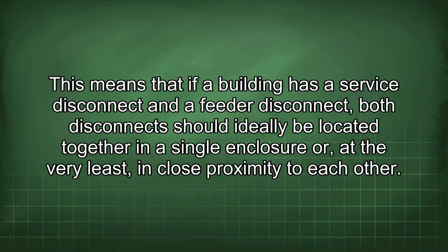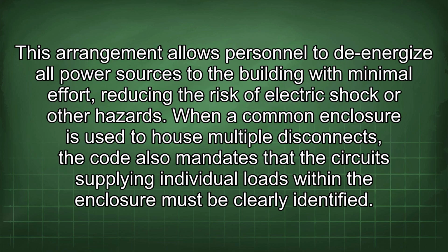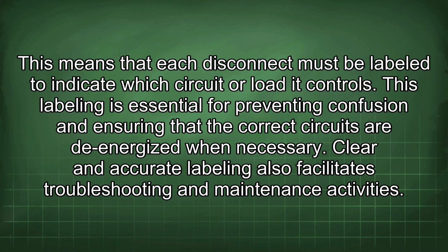serve. This means that if a building has a service disconnect and a feeder disconnect, both disconnects should ideally be located together in a single enclosure or, at the very least, in close proximity to each other. This arrangement allows personnel to de-energize all power sources to the building with minimal effort, reducing the risk of electric shock or other hazards. When a common enclosure is used to house multiple disconnects, the code also mandates that the circuits supplying individual loads within the enclosure must be clearly identified. This means that each disconnect must be labeled to indicate which circuit or load it controls. This labeling is essential for preventing confusion and ensuring that the correct circuits are de-energized when necessary.